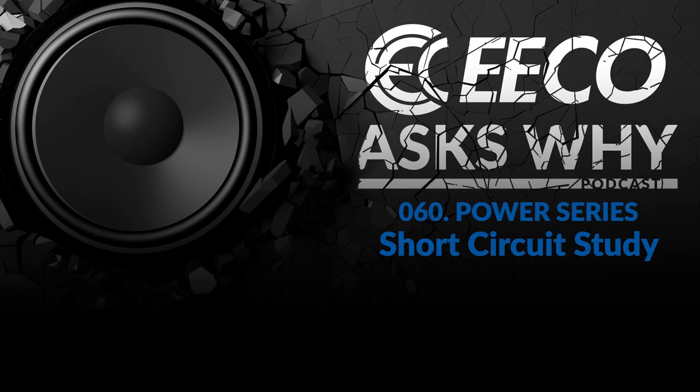My recommendation for a short circuit study, based on experience, is that it be completed at least every 5 years, due primarily to the changing utility demand. The majority of the fault current in any system is going to come through the utility. A smaller percentage of the contribution will come through motors, synchronous generators, and so forth during a fault. But the overwhelming majority of the fault current will come through the utility.